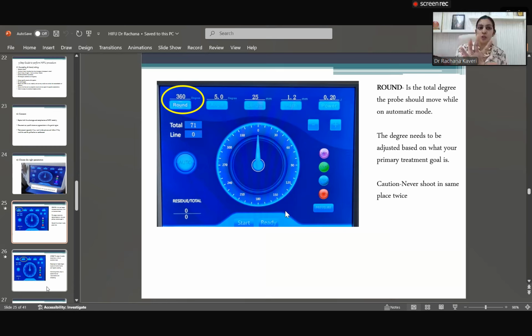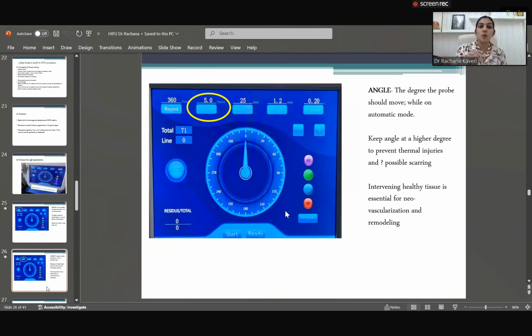So once you put it on automatic, you put the probe inside and you just hold, so that the probe moves at equal distance and covers the entire circle, whatever you want to do. Never shoot the same place twice, because that increases the chances of a fistula, which you do not want to get into. Now, the next parameter that we're talking about is the angle.